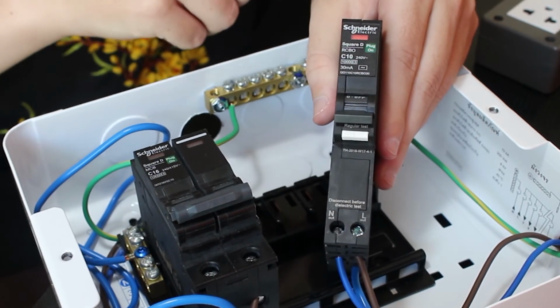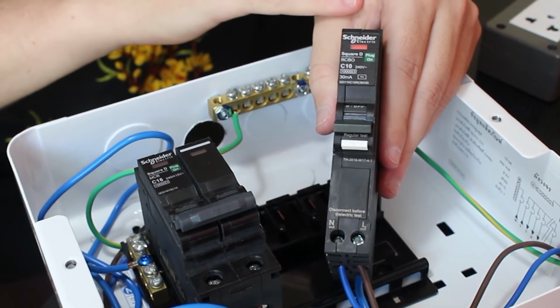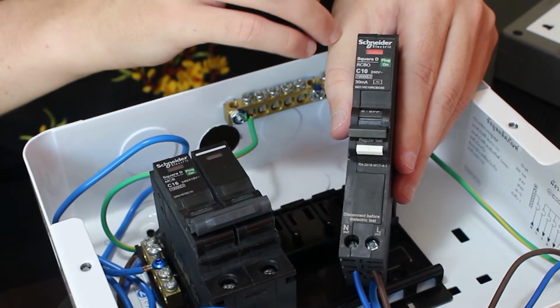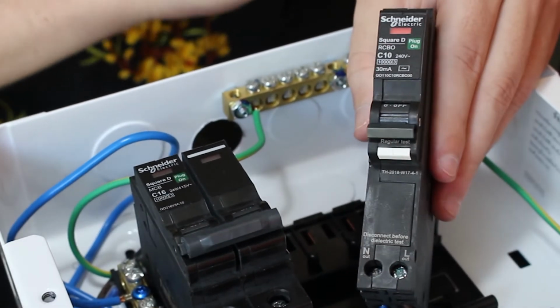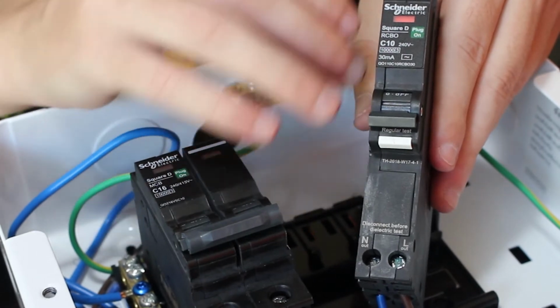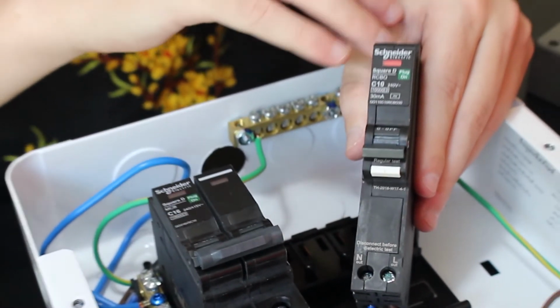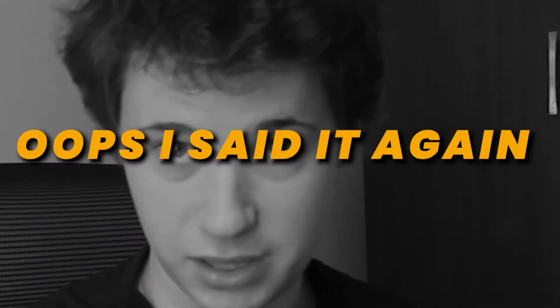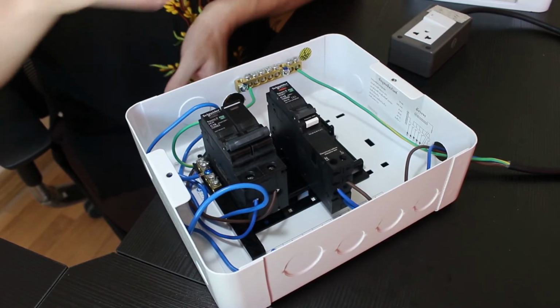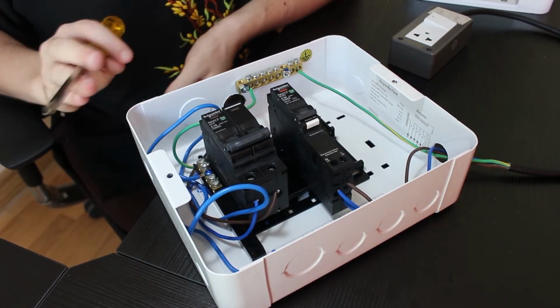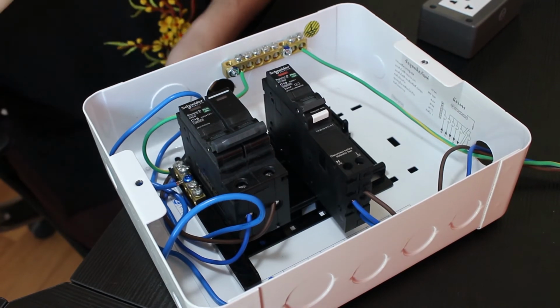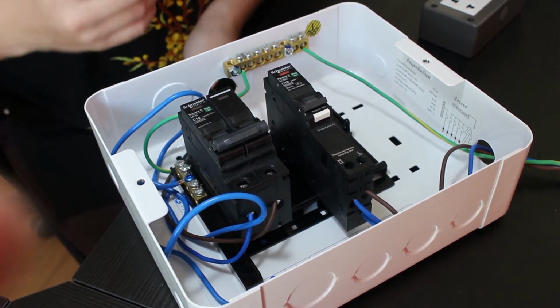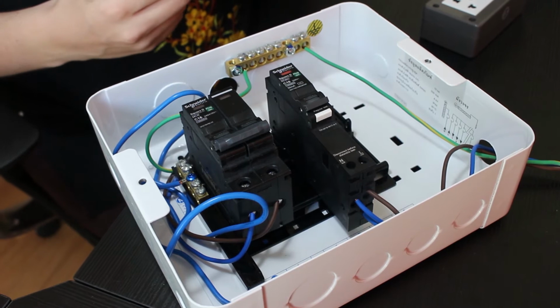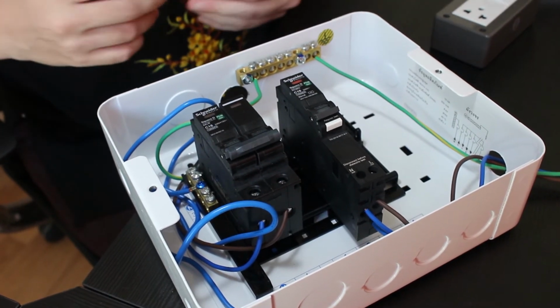That's why in our case 30 milliamps might be a little bit overkill, and it would be safer to get a lower rating, because we are only testing one electronic device, so there is not going to be that much leakage coming from somewhere else. It's only for safety in our case, so the lower the better. In that precise wiring, I'm using the Schneider system because that's the one I got available around here and I tend to trust them. As far as I'm trying not to die, finding a brand to trust is certainly a good idea.